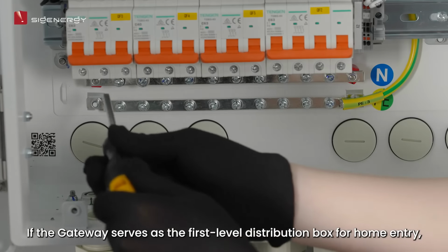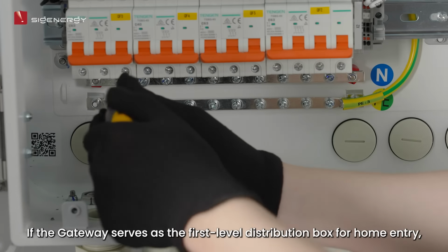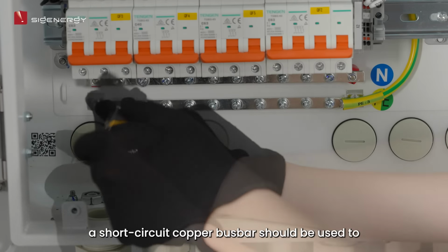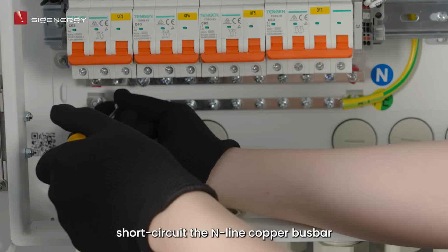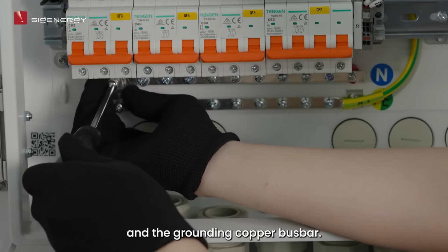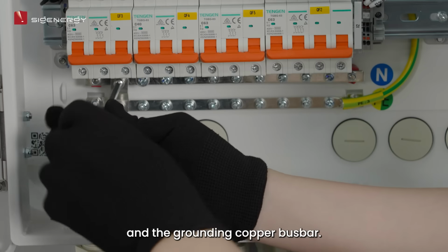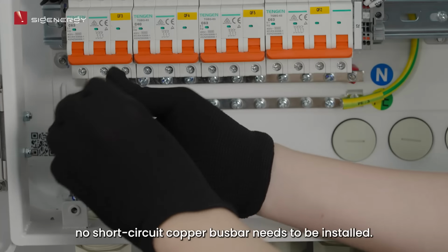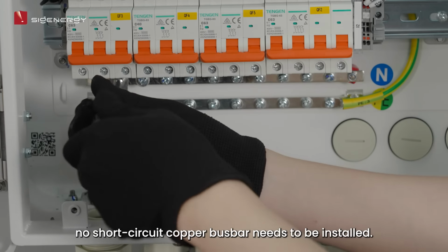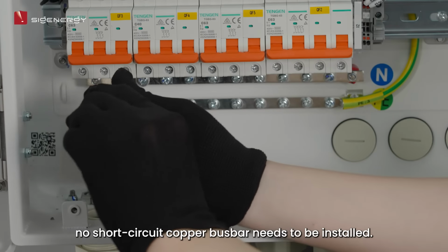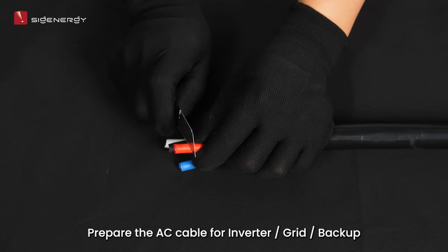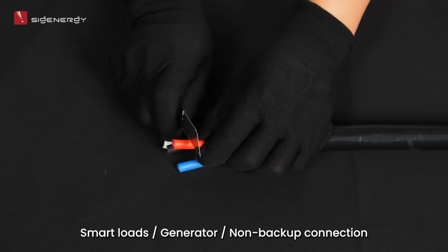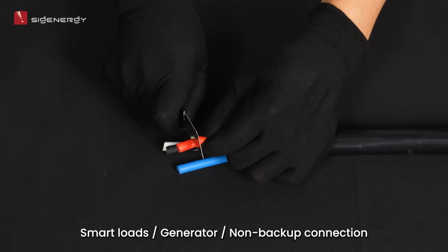If the gateway serves as the first-level distribution box for home entry, a short-circuit copper bus bar should be used to short-circuit the N-line copper bus bar and the grounding copper bus bar. In cases other than the above, no short-circuit copper bus bar needs to be installed. Prepare the AC cable for inverter, grid, backup, smart loads, generator, non-backup connection.